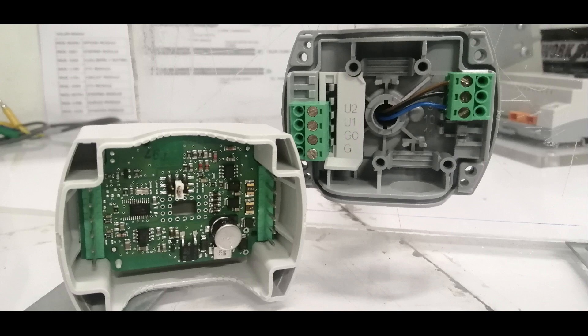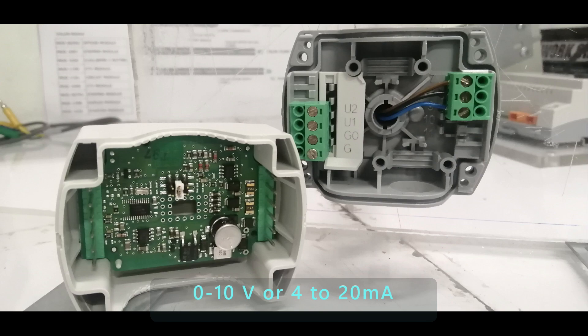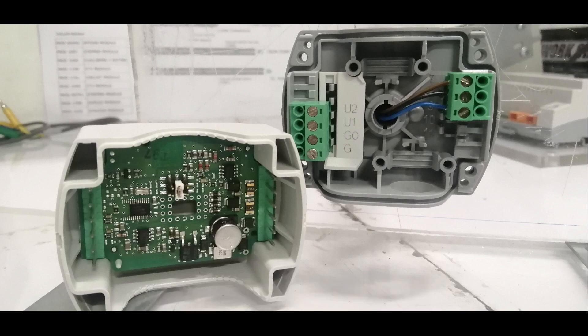Inside the sensor head is a circuit board. The electronic measuring circuit converts the sensor's signal to a continuous DC 0 to 10 volts or 4 to 20 milliamp signal which corresponds to temperature and relative humidity values.